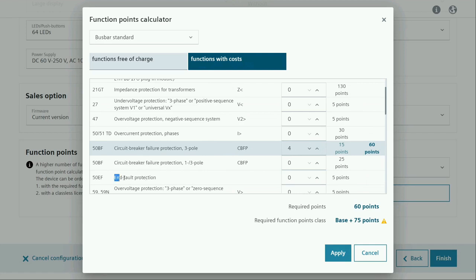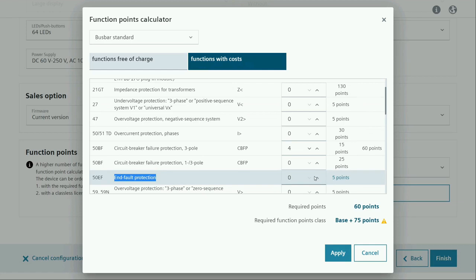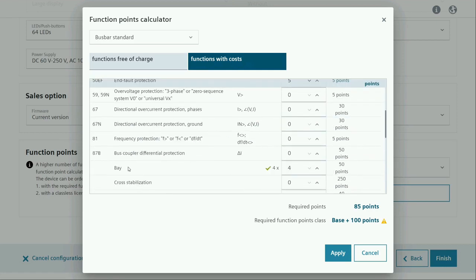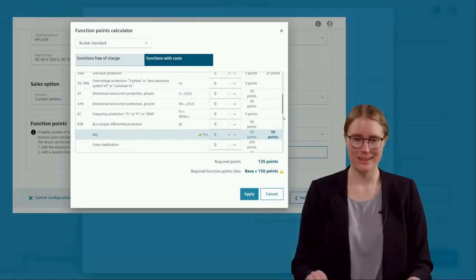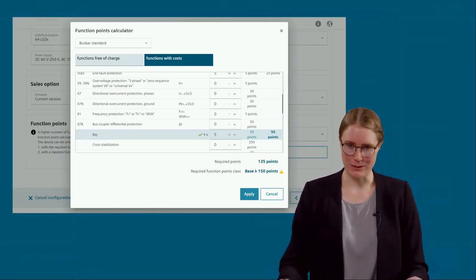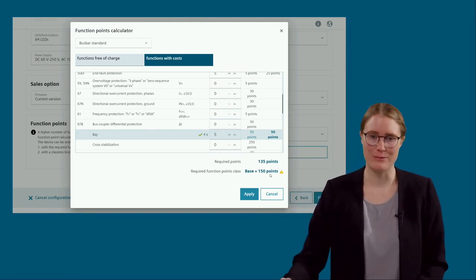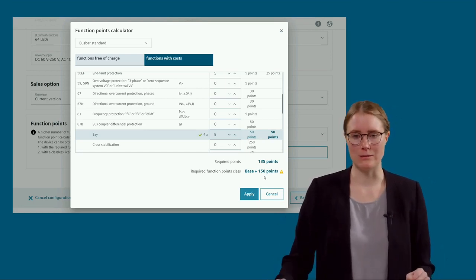Then I also add the endfault protection, which is always recommended for the busbar protection. I increase this number up to 5, because this is also interesting for the coupler bay. Also important, we have to increase the number of function points for an additional bay, because in the significant feature we chose, only 4 bays were included, and we have 5 bays in the setup. So I increase the number from 4 to 5 here. Let me check my notes. I think this should be all for our centralized busbar protection. So we need 150 additional points. Actually we need 135, but the next higher function point class would be 150.